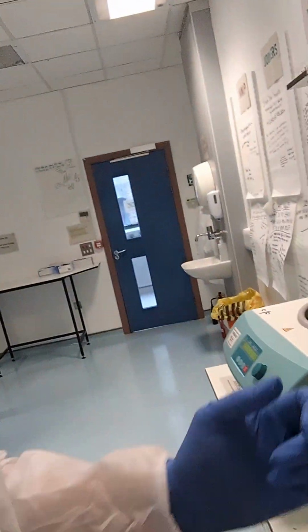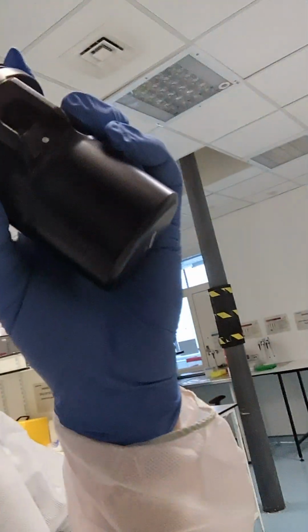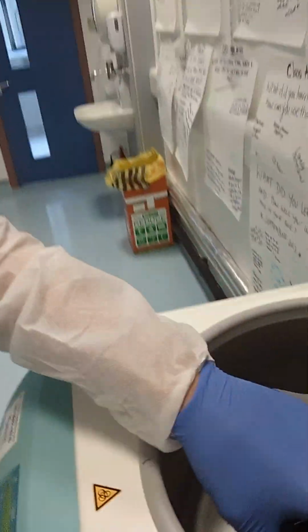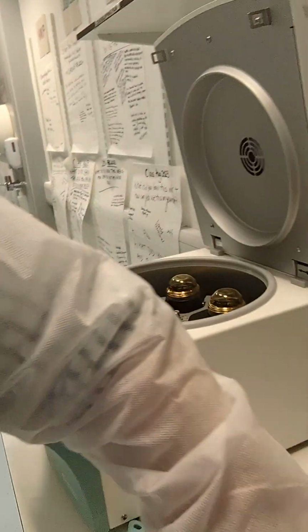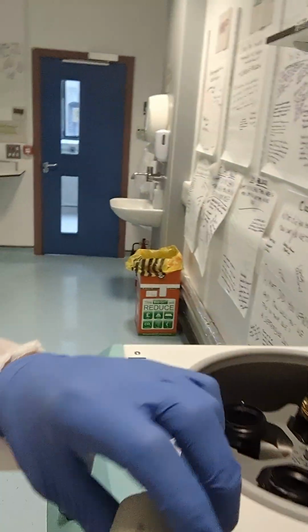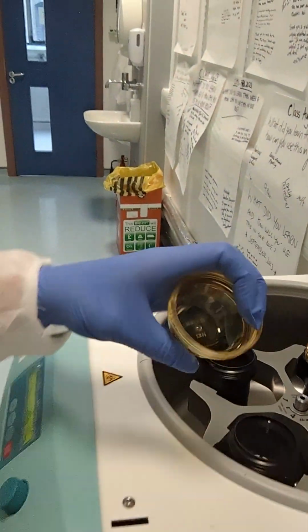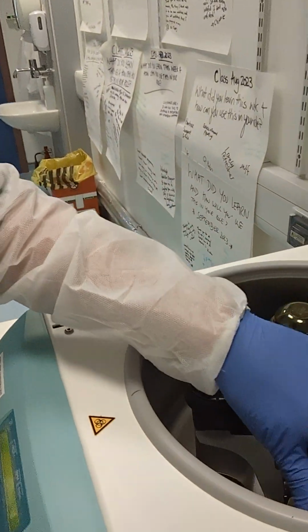Once the adapter, bucket and lid have been in the Virkon for half an hour, you can remove them, you can surface dry them with a tissue, and you can rebuild the centrifuge, which I've shown you in previous videos. But the bucket sits in the rotor, make sure it can swing. The adapter needs to be dried inside and out, and the lid will need to be dried. And that is how you deal with a broken sample. And like I said, it happens very infrequently if the centrifuge is used properly.